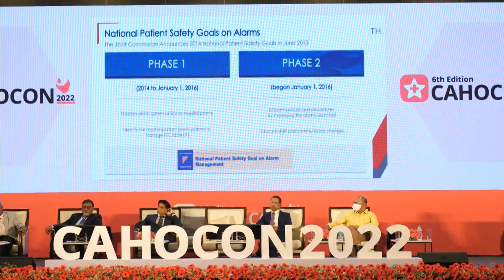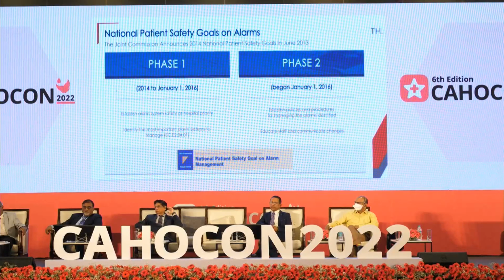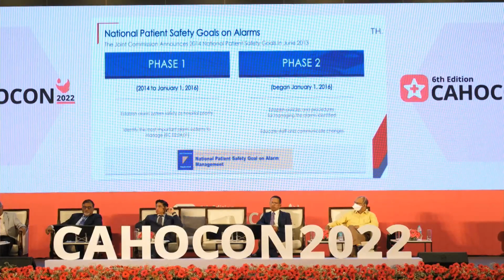The purpose of the clinical alarm is to enhance patient safety, and a perfect alarm system should never miss an event and never alarm when there is no event. Most commonly, nuisance alarms are caused by lead displacement and/or alarm settings that are not customized to the patient. For example, a COPD patient may have a saturation of 88 at home, but if the SpO2 alarm is kept at 90, it will go on continuously. So there is a general agreement that alarm fatigue is a major safety issue, and hospitals have to analyze their own situation and implement strategies to better manage the alarms.